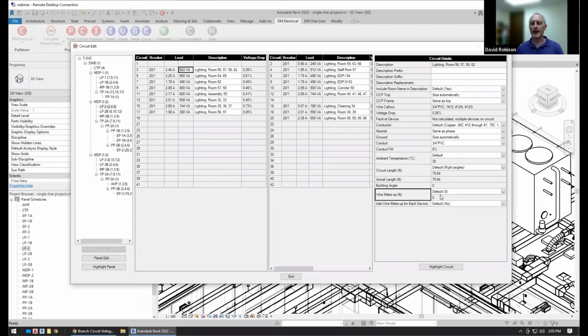Then we have the wire makeup. This is additional wire length added either once to the circuit or for each device. Say, for example, you're in a warehouse and you're running your circuit on the ceiling and dropping down to receptacles. It's a 20-foot ceiling and you've got an extra 40 feet of wire to each receptacle. You could set a wire makeup and do that for each device on the circuit, in this case light fixtures. And so we've got a hugely larger circuit length now. That's how you can account for those additional distances.